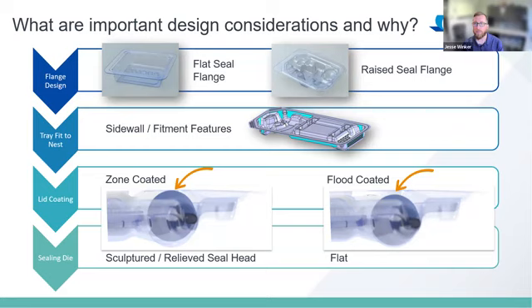I know Lynn's going to touch on that a bit as well. The next things to consider are the tray sidewall features. As we're designing a tray, we're looking for ways to get sidewall contact that can locate the tray within a seal nest for repeatability. So if we have a really flat tray, sometimes it can be difficult to orient the tray within a nest, or if we don't have good sidewall contact, things can go in one way one time and a different way the next time. So we really want to be looking at that from a tray design standpoint as well as we're laying out a tray.